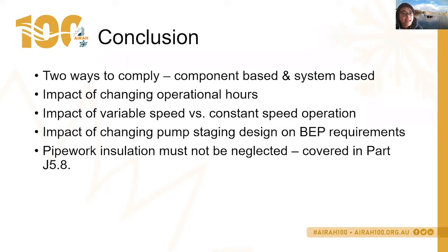We also looked at the impact of changing your pump staging design. So we went from lead lag to duty standby, which equates to higher flows without changing pipework, which means that now my velocities through some stretches of pipework will be higher. And you can see that doing that leads to a higher BEP. So now we need 81.3% instead of something lower in a duty standby, lead lag configuration.